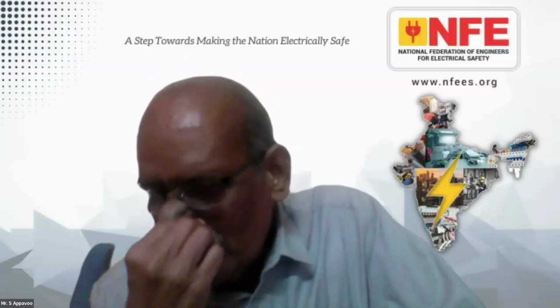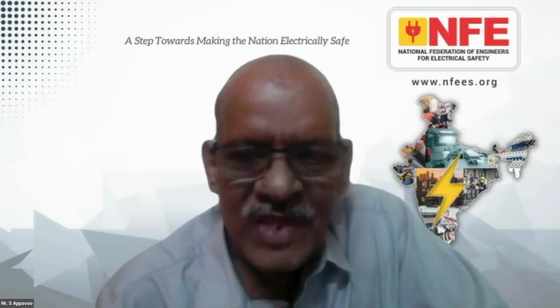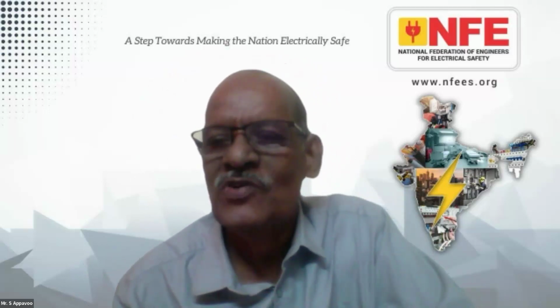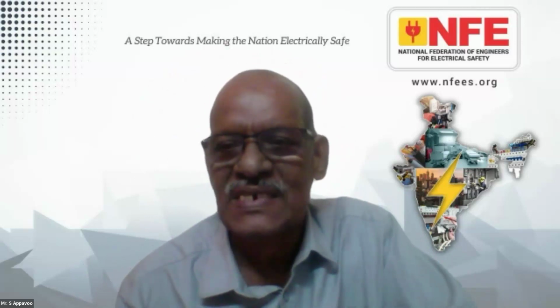Another question is, someone has asked whether the harmonics is coming from outside or inside. For that, multiple meters are available in the market. In the case of Schneider, there is the ION 9000 series meter. If you place that, you will be able to get data on whether the harmonics is coming from outside or is being generated by the load you have. So there are multiple ways to find this out. You can also contact Mr. Abhishek when doubts arise. One person asked whether it is within the building or from outside the building. It's a valid question.